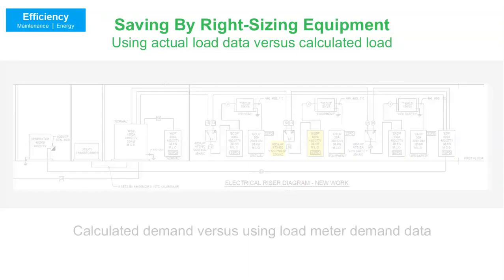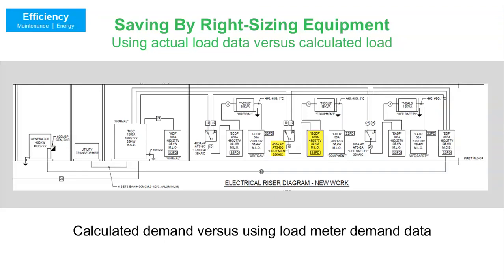And then the final example that I want to give you is what many would refer to as right-sizing equipment. In my experience, much of the power equipment in hospitals is dramatically oversized. Here's a real quick example. This is a project I've got highlighted: a transfer switch feeding a new panel board. We're going to look at calculated demand versus actual demand.